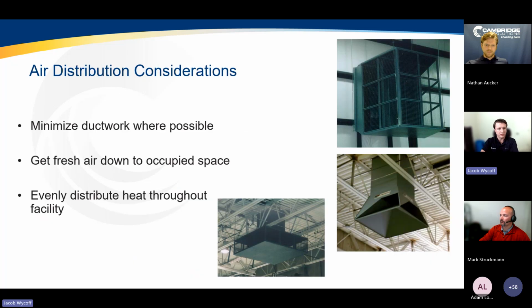And for air distribution, you want to minimize ductwork where possible. As I mentioned, this is just going to reduce the cost of installing ductwork and also reduce the chances of that ductwork getting hit by a forklift or some other things happening in the space. Really, whenever you're thinking about air distribution, we want to make sure we get that fresh air down to the occupied space. We don't want to be short cycling that fresh heated air straight through an exhaust fan. We want to make sure that fresh air gets down to the space where the people are, and we're evenly distributing the heat throughout the facility so that all the occupants are comfortable.